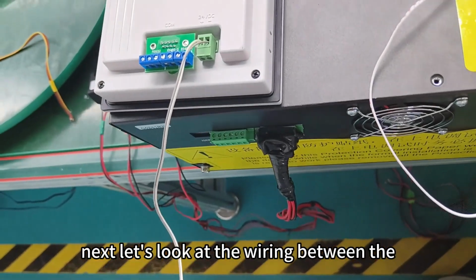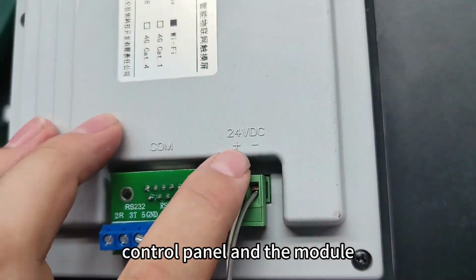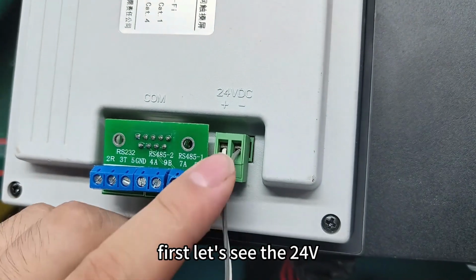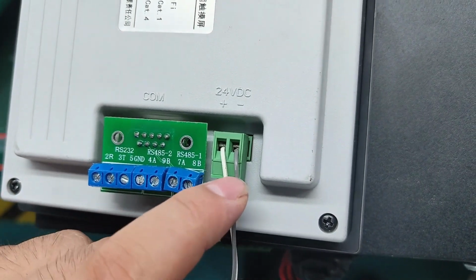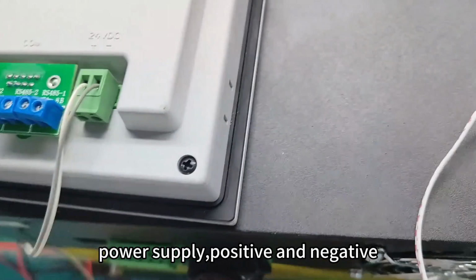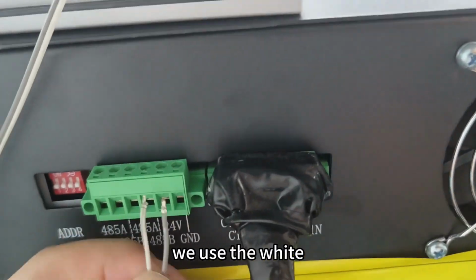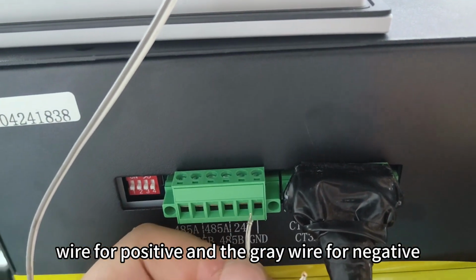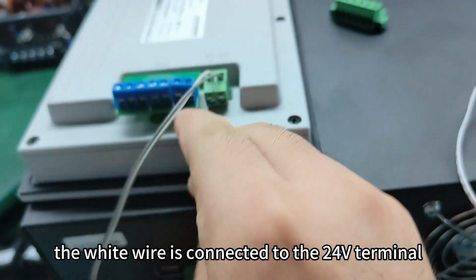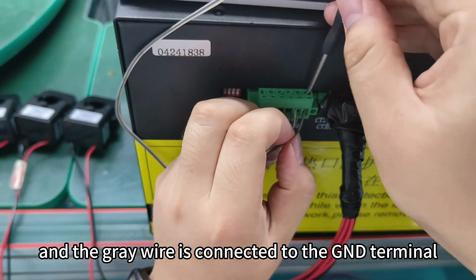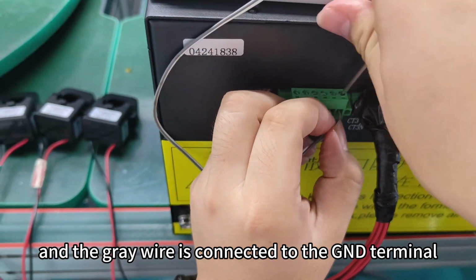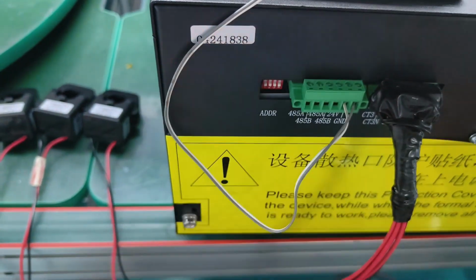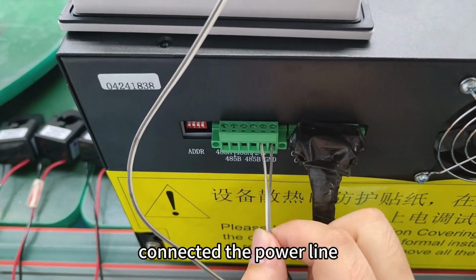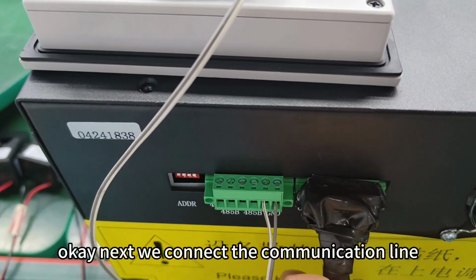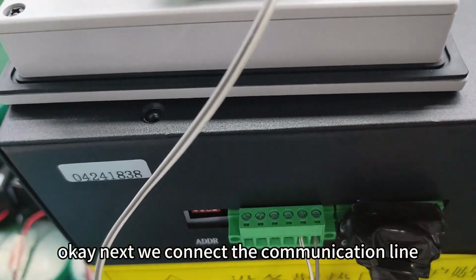Next, let's look at the wiring between the control panel and the module. First, let's see the 24 volts power supply, positive and negative. We use the white wire for positive and the gray wire for negative. The white wire is connected to the 24 volt terminal and the gray wire is connected to the GND terminal. Okay, now we have already connected the power line.